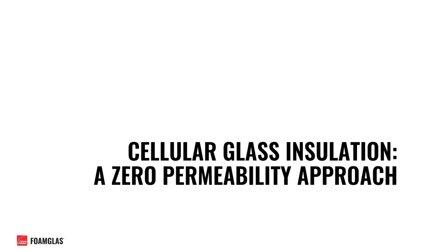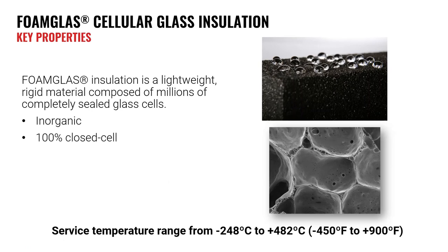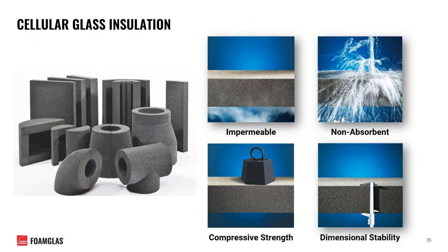With all of this taken into consideration, one solution in particular to consider for these types of systems is cellular glass insulation — a zero permeability approach. Cellular glass insulation is a lightweight, rigid material composed of millions of completely sealed glass cells, with a wide service temperature range from minus 450 all the way to 900 degrees Fahrenheit. Foam glass insulation is completely impermeable with a water vapor permeability rating of zero, and does not require the use of a separate external vapor barrier — the insulation itself acts as its own vapor barrier.